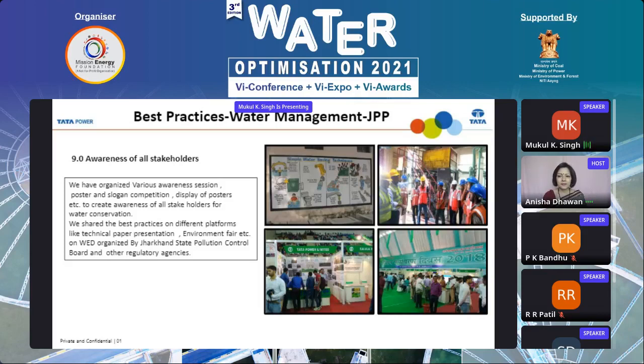And we have shared our best practices for water conservation at different forums of pollution boards, in the programs organized by pollution control boards, MOEF, and other regulatory agencies. Apart from these initiatives, which I have tried to list, we have taken many more initiatives to reduce the water consumption, like maximizing the dry fly ash utilization. Whatever fly ash is collected, 80% of ash is collected in dry form. We try to utilize most or 100% in the dry form. Otherwise, we have to carry it to the ash pond by water, hydraulically. Also, we are trying to procure low ash coal so that the whole ash content of generation is reduced.